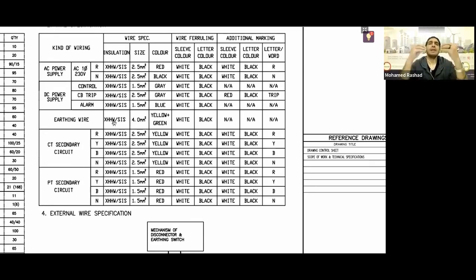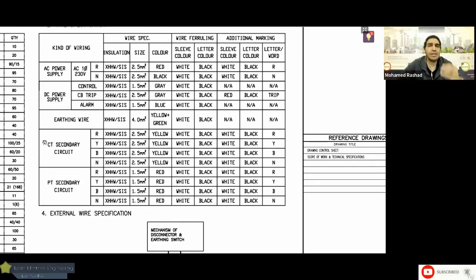So what's the idea? The idea is that the cables they use have a certain standard. They tell you this cable inside the control circuit, if a short circuit occurs, God forbid, it causes a spark, so the wire is supposed to not catch fire if a spark occurs. We brought a lighter, and when you hold it to the wire, it catches fire, so its insulation is not the required type. It's not like working with electricity at home connecting a bulb with any wire. Here we're working in control circuits related to GIS, dealing with equipment worth millions and circuits where mistakes cannot happen. You must be very careful with all the technical specifications in your directory.